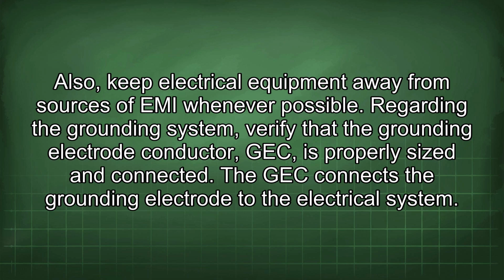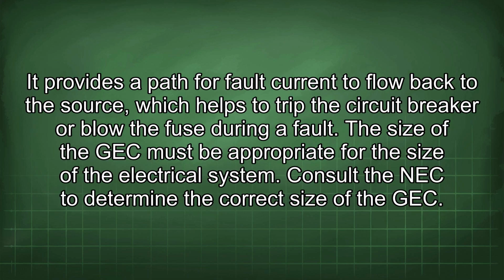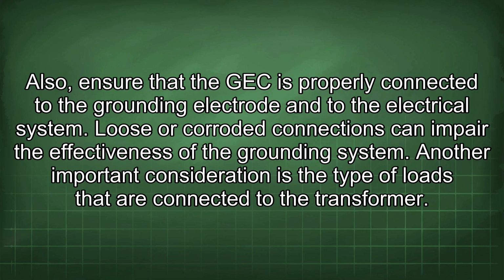Regarding the grounding system, verify that the grounding electrode conductor (GEC) is properly sized and connected. The GEC connects the grounding electrode to the electrical system. It provides a path for fault current to flow back to the source, which helps to trip the circuit breaker or blow the fuse during a fault. The size of the GEC must be appropriate for the size of the electrical system. Consult the NEC to determine the correct size of the GEC. Also, ensure that the GEC is properly connected to the grounding electrode and to the electrical system. Loose or corroded connections can impair the effectiveness of the grounding system.